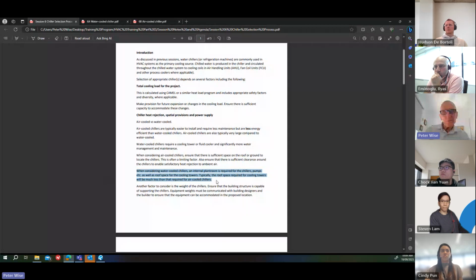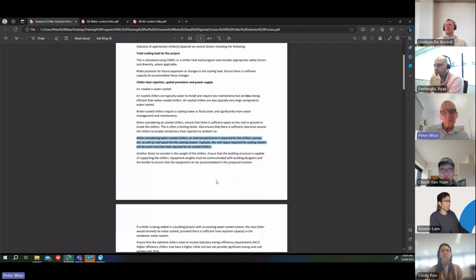Another factor to consider, talking about dimensional things, is the weight of the chillers. Ensure that the building structure is capable of supporting the chillers. Now, this sounds like, you know, well, the building should be fine, but this is important to make sure that the building designers and the builder themselves are aware of the weights. They'll normally ask for that anyway, so that the equipment can be accommodated in the proposed location.